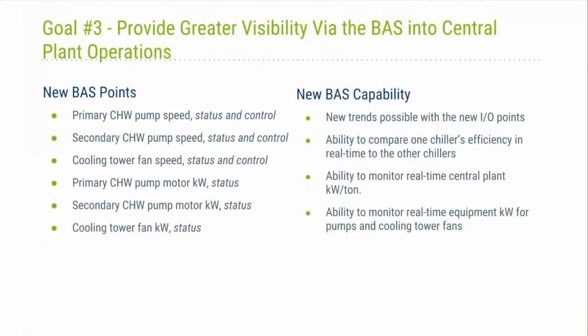Goal number 3, provide greater visibility into the central plant equipment via the BAS so as to improve system monitoring and troubleshooting. On a previous slide, we discussed some of the instrumentation and hardware required for demand flow. Besides improved system performance, another result was new BAS inputs and output points and the ability to perform new trends with all this new data we were receiving.